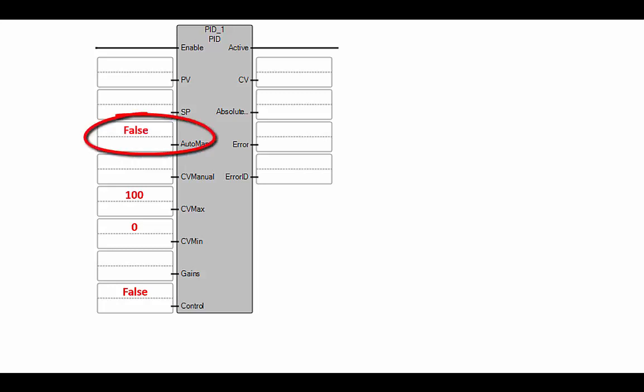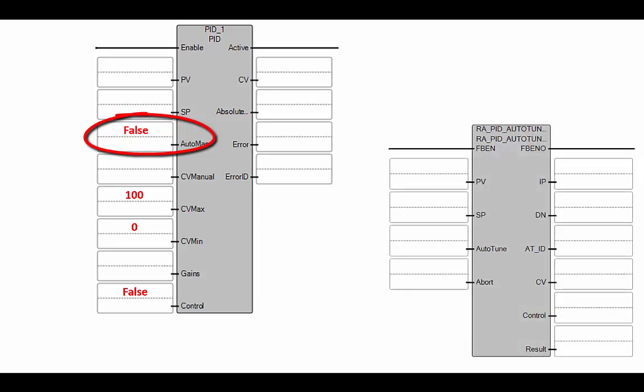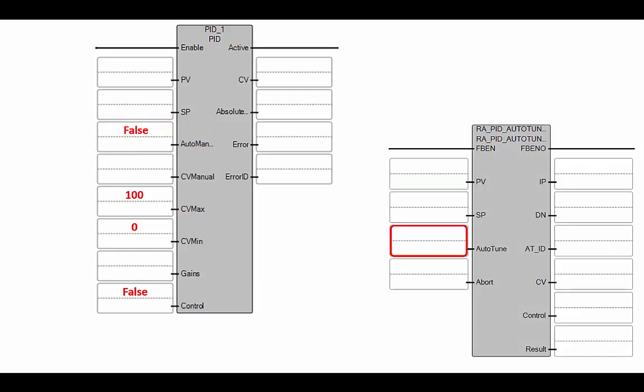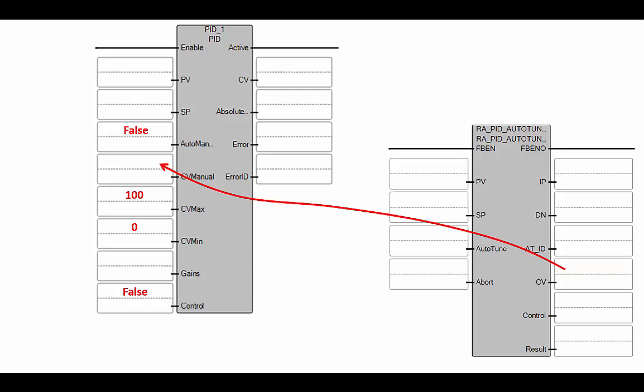If we set the auto or manual mode to false, that puts the PID controller in manual mode — and that's what we need to do if we want the auto-tuning instruction to take over. The auto-tuning instruction has an input for the process variable and the set point, and if we set this auto-tuning mode to true, the auto-tuning sequence begins and calculates its own control variable. That control variable needs to be passed into the manual control variable input of our PID, because when the PID is in manual mode, that manual CV is what gets passed to the CV output controlling the process.